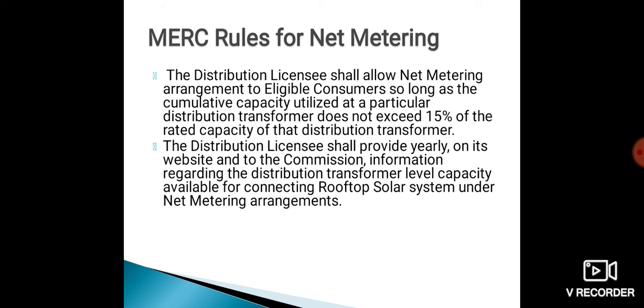What are the next rules? The distribution licensee shall allow net metering agreements to eligible consumers so long as the cumulative capacity utilized at a particular distribution transformer does not exceed 15% of its rated capacity. That means if the distribution transformer has a capacity of 100 kVA, you should not add more than 15 kVA back to the supply.